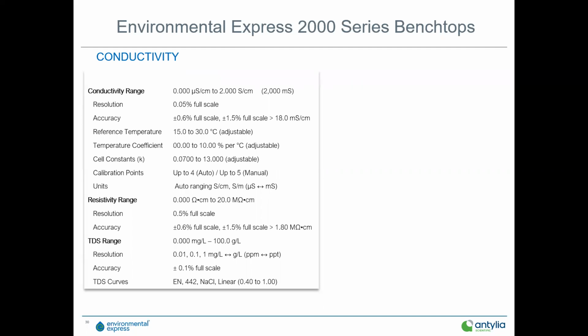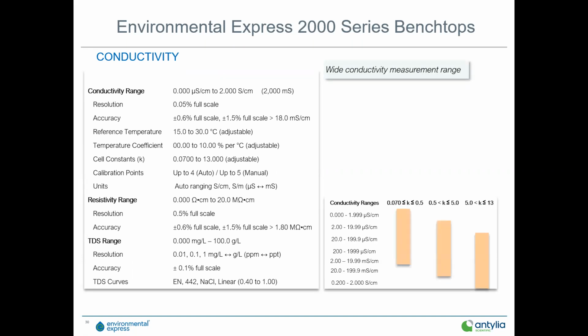TDS curves, as I mentioned, the EN curve, that's the DIN curve, 7888. The 442 curve for naturally occurring water, sodium chloride, or linear, those all being adjustable. And then the ranges of some of the cells. Obviously, the conductivity cells from different manufacturers have some different ranges. A 0.1 is going to do your real low end measurements. Now, some folks' cells go up to 20 to 40 microsiemens with that 0.1 cell. Some will go up much higher. In this case, we'll actually go up to millisiemen range.